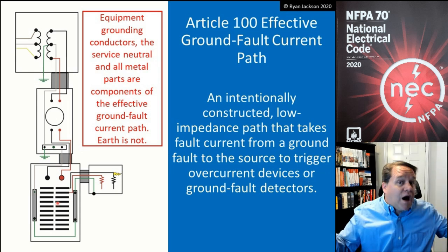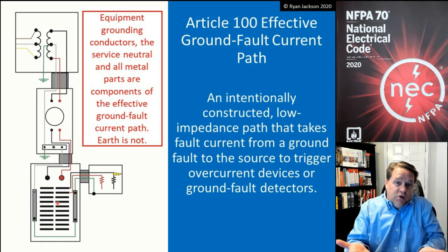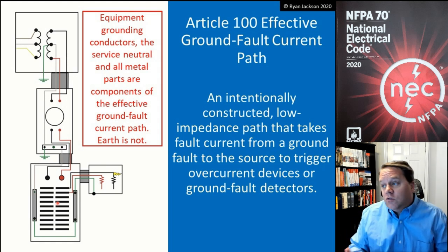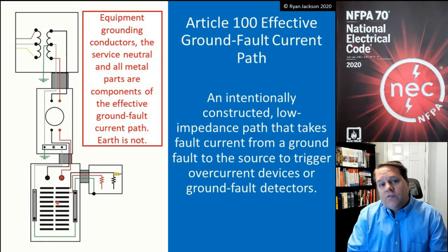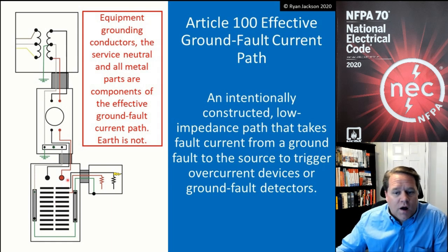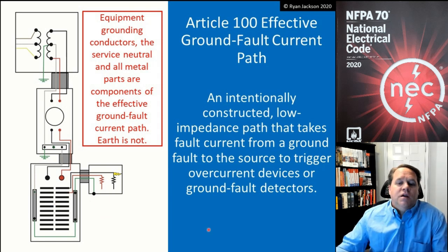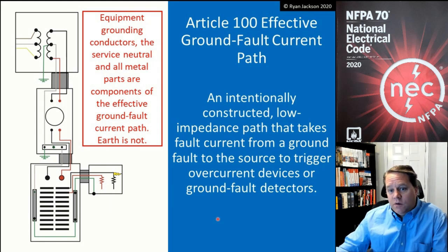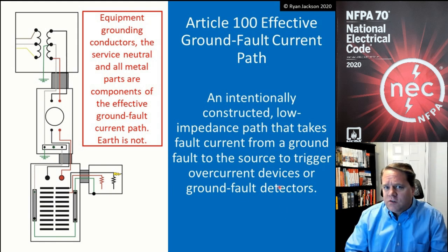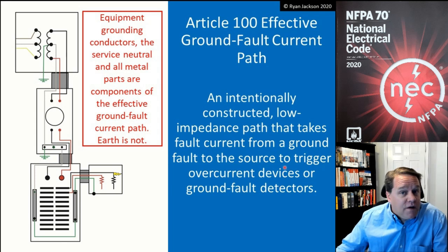200 or 2,000 or potentially, I mean, look, it could be as high as 100,000 or sometimes even more amperes. So that massive amount of current is going to do what? It's going to trigger the overcurrent device, whether it's a breaker or a fuse. And again, if it's an ungrounded system or a high impedance grounded neutral system, then it would initiate ground fault detectors. But those are pretty unusual.